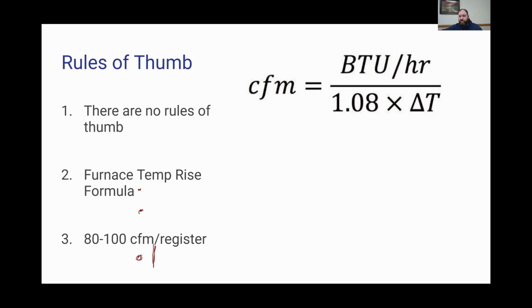In our state, we have a lot of furnaces in the basement with air conditioners or heat pumps attached to them. Most of our homes are designed for a 6-inch duct run to have 80 to 100 CFM through it. So one thing I do with customers is I say, okay, let's count how many registers you have. And if we count 6 registers and they have a 2-ton air conditioner on a 60,000 BTU furnace, 6 registers is only good for about 600 CFM. Well, a 2-ton air conditioner needs 400 CFM per ton, so it needs 800 CFM. And that 60,000 BTU furnace is going to want more than that. So, every furnace that comes from a manufacturer comes with a recommended temperature rise.